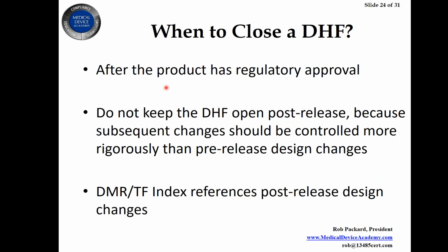That also helps you evaluate whether you need to do a catch-up 510K because you have a cumulative number of changes that is so great that even though each change by itself wasn't great enough to necessitate a 510K for device modification, the cumulative changes is great enough you need to do a catch-up 510K. And some companies will just do that as a matter of course. They'll do that periodically to make sure that when the FDA comes through an inspection, they don't get a finding.